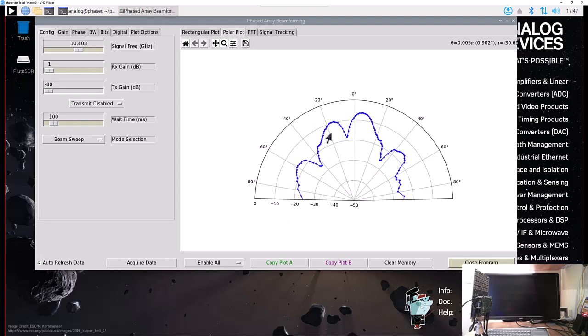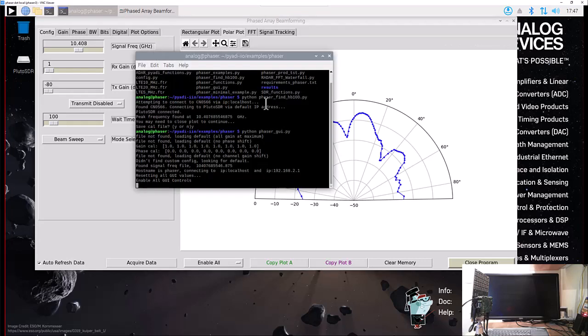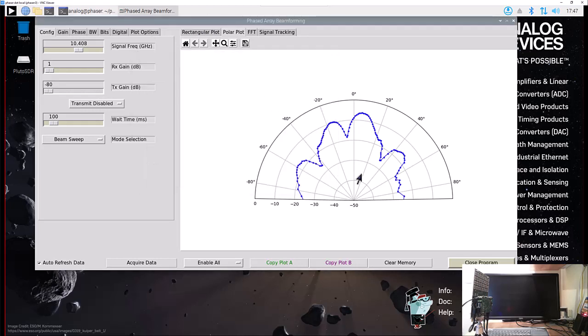And the reason that's the case is if we look at the initial output, we notice that we don't see a gain calibration or a phase calibration file. So the array isn't calibrated. We haven't done any adjustments to account for manufacturing variations and channel-to-channel variations here. But let's get a rough idea of whether it's operating at all.